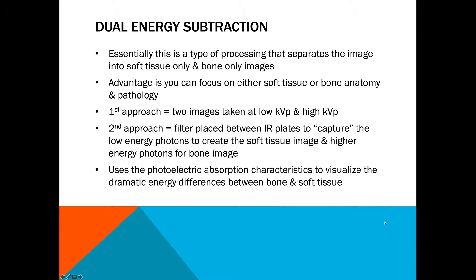Dual energy subtraction is a process that separates soft tissue from bone so that you can see only the soft tissue or only the bone in the image. The advantage is that you can focus on either soft tissue or bone anatomy and pathology, especially if it's hidden behind something. The first approach is to take two images — one at a low kVp and one at a high kVp in quick succession while the patient holds their breath. The second approach uses an actual filter placed between the IR plates to capture low energy photons for the soft tissue image, while high energy photons passing through the filter create the bone image.